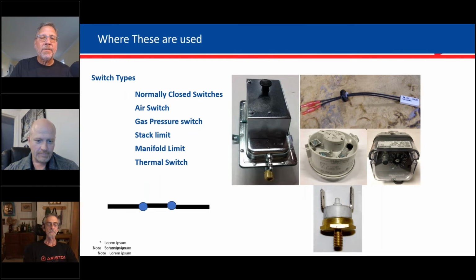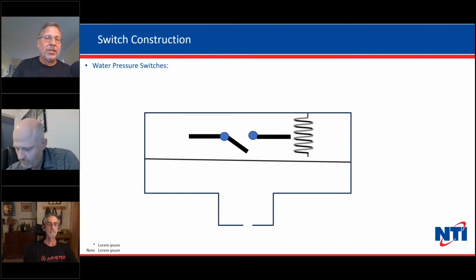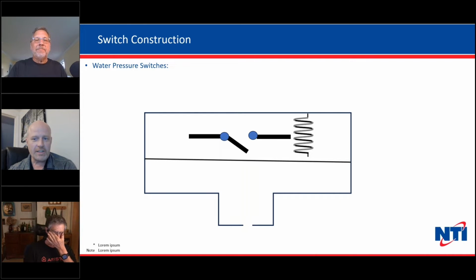No, it's good you brought this up because that's something new to the NTI that guys are seeing. So in the case I had, the entire heat exchanger inside was full of calcium and the supply return sensor could not sense the temperature. So the burner kept on firing because it couldn't get to 180 and it started to melt the door. Now this will turn it off. Absolutely. And back in the day with the old TI series, I actually did see a couple of burner doors melt off of boilers in similar situations. The heat exchanger was in catastrophically bad shape, and the burner is hot enough to melt everything the boiler is made of, with the exception of those white refractories. Everything else, it's plenty hot enough to burn if it doesn't have water cooling it off. That had to be pretty hot. Oh yeah.